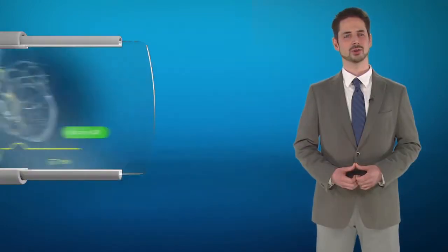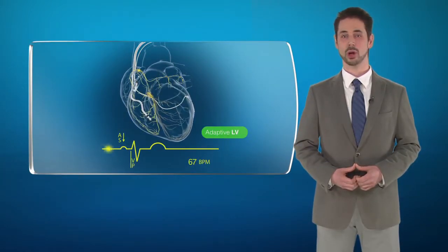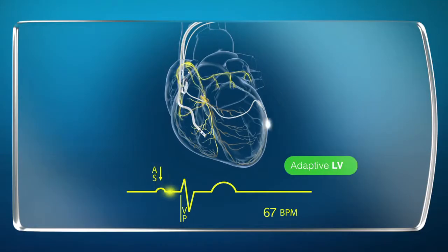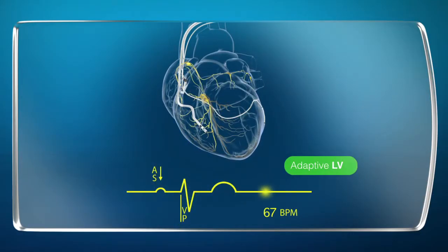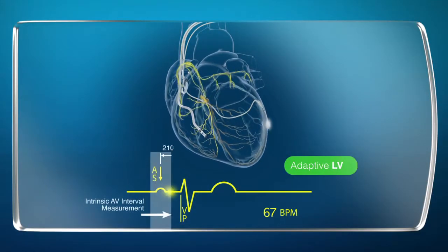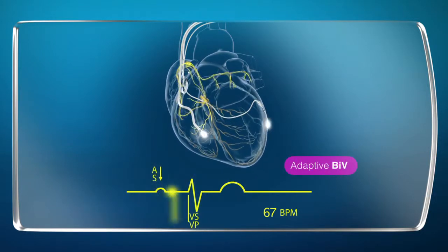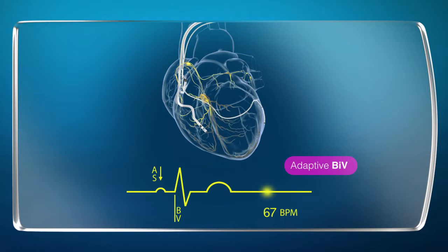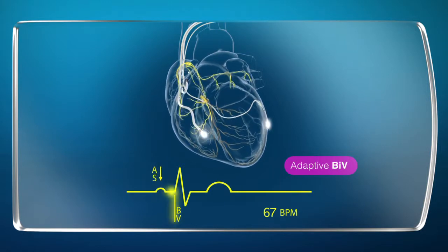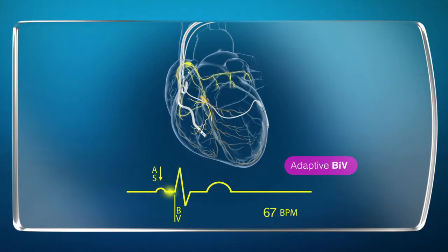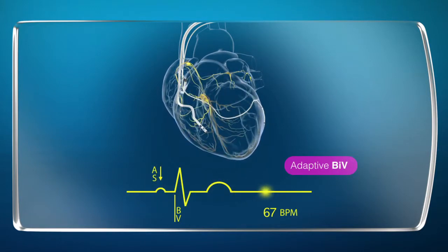If AV conduction is normal and heart rate is below 100 beats per minute, Adaptive CRT provides LV pacing that is synchronized to preempt intrinsic ventricular conduction. Otherwise, Adaptive CRT provides biventricular pacing that is applied after the end of the p-wave but before intrinsic ventricular conduction. Interventricular delay is adjusted to provide left ventricular pre-excitation in patients with better preserved conduction.